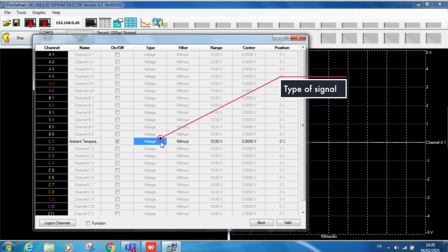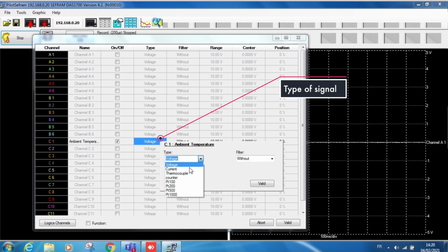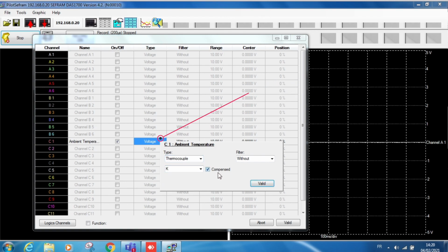The type is a temperature measurement via a K-type thermocouple. Then, let's set up a 1 Hz filter. Since this is a temperature measurement, we will cut all frequencies above 1 Hz.